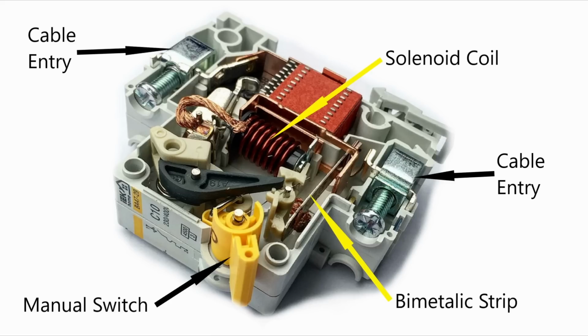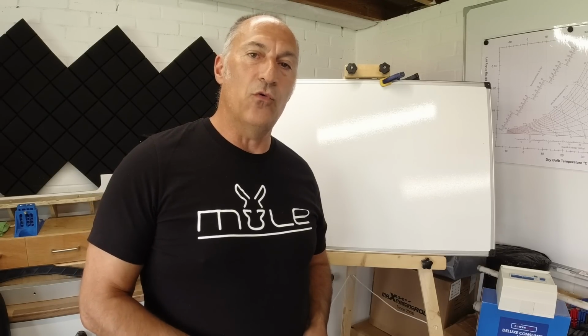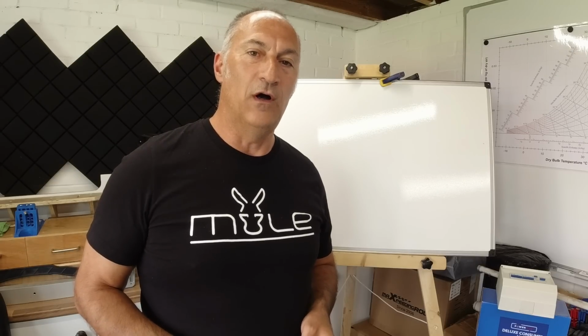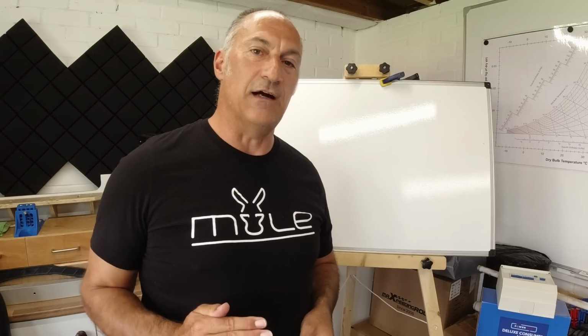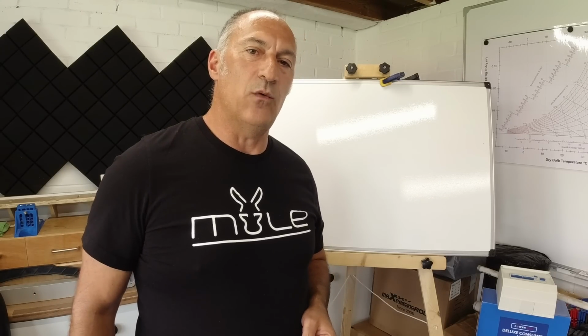With a very large overcurrent, this will obviously heat up really quickly. And if there is a huge current flowing through the device, a magnetic field builds up in the solenoid coil, which trips the device almost instantly. Once the fault has been rectified and the device has cooled down, the switch can be manually reset. So you can see there that the MCB gives us two types of protection depending on how much overcurrent there is. If it's a very small overcurrent because we've just plugged in too many devices, it may be a long period of time before that little bimetallic strip curves enough to break those contacts. So we just need to be aware of that.